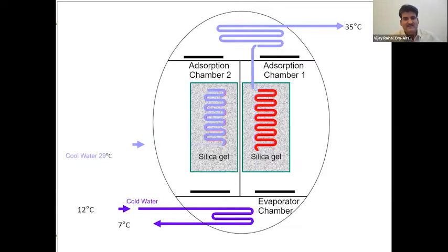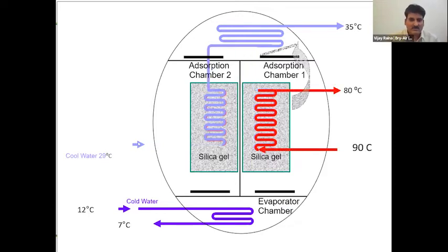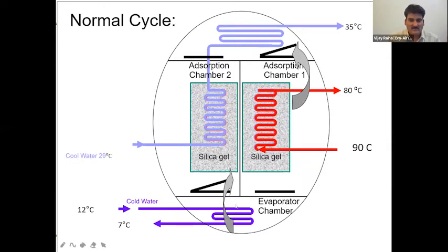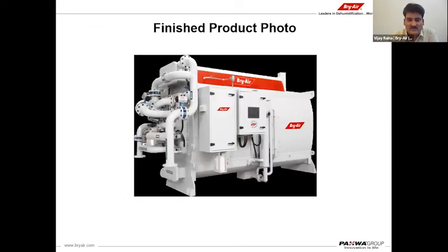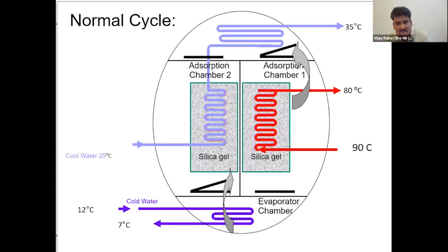So there is a mass transfer happening in chamber 1 and chamber 2, and now the refrigerant goes from chamber 2 to the condenser on top of that. So see, these 2 diagonal flappers are on. It is a simple construction chiller. There is nothing outside going inside the chiller. It's a complete single shell chiller, and the single shell is maintained under vacuum, and refrigerant is moving from one heat exchanger to another heat exchanger through silica gel technology. So this was the basic cycle of how it works and how we transfer the heat from chilled water to refrigerant water. Then the refrigerant water moves from the evaporation chamber to the condenser, giving heat to the cooling tower and coming back as a pure liquid refrigerant in the evaporation chamber to complete the chilled water cycle.